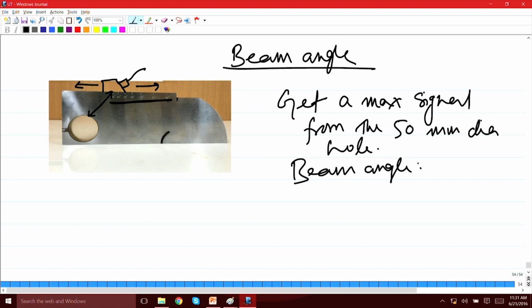Okay. So, this top surface that you have, if you keep it over here, this can be used for angles in the range of 45 to 60 degree, and for higher angles you could keep the probe over here on this surface. Okay. So, this will be 60 to 70 degree, because if you have seen the angles, the higher angles are on the lower side and on the top side this is the range. Okay. So, this is how you first get to know the angle. Okay. Once you have established the index point, you get the beam angle.